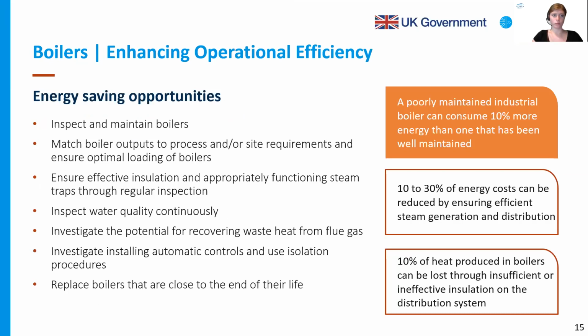If you look at these pointers on the boiler, they are all action words: inspect, match, ensure, inspect, investigate. They are actually best practices or ideal considerations an operational routine should have. For instance, it's definitely important to inspect and maintain boilers. A poorly maintained boiler can consume 10% more energy than one that has been well maintained.